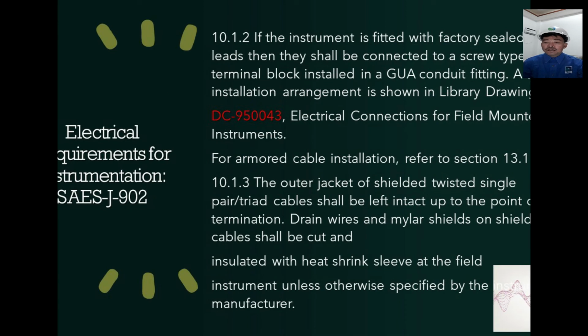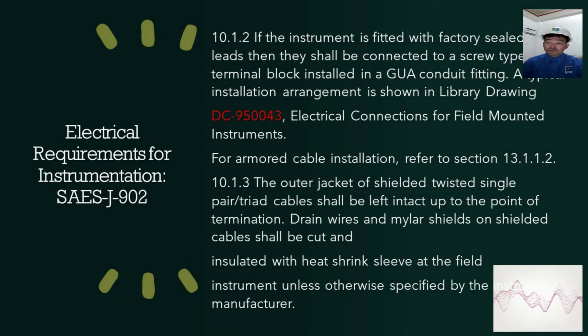For armored cable installation, refer to section 13.1.1.2. The outer jacket of shielded twisted single pair triad cable shall be left intact up to the point of termination. Drain wires and mylar shield and shielded cable shall be cut, insulated with heat shrink sleeve at the field instrument unless otherwise specified by the manufacturer.